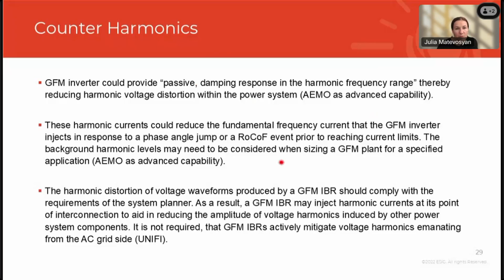AEMO also says that when providing these harmonic currents, the capability to provide other grid forming functions may be reduced. And so when sizing a grid forming plant, one should think about background harmonics at the connection point. And then UNIFI specifically says that harmonic distortion of the voltage waveform produced by grid forming should comply with requirements at the connection point. With that, maybe grid forming is helping to mitigate some of the harmonics on the grid, but there shouldn't be a requirement that grid forming mitigates harmonics on the grid just as a purpose.